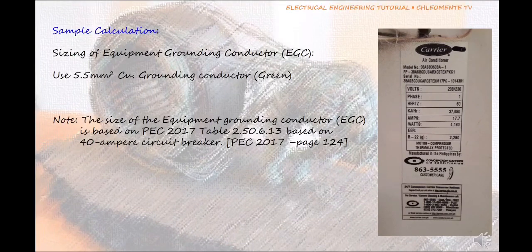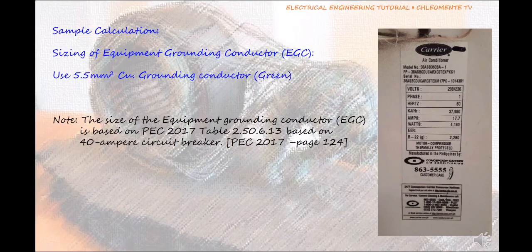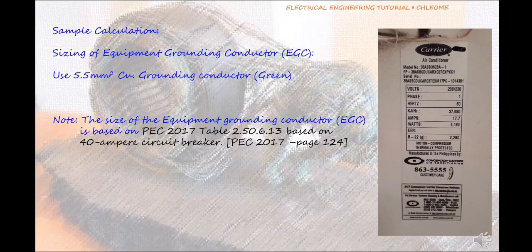Sizing of Equipment Grounding Conductor, EGC. Use 5.5 square millimeters copper grounding conductor, green. Note: The size of the Equipment Grounding Conductor (EGC) is based on PEC 2017 Table 2.50.6.13 based on 40 ampere circuit breaker, PEC 2017 Page 124.